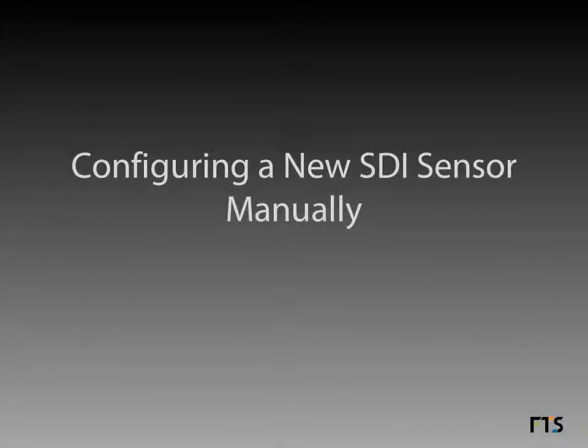Configuring a new SDI sensor manually. SDI sensors are so called because they communicate to the data logger via the widely used Serial Data Interface, or SDI protocol. SDI sensors are plugged into data logger front panel connectors marked SDI-A, SDI-B, SDI-C, or SDI-D. This presentation shows how to configure an SDI sensor manually, which is the currently recommended procedure for most SDI sensors.